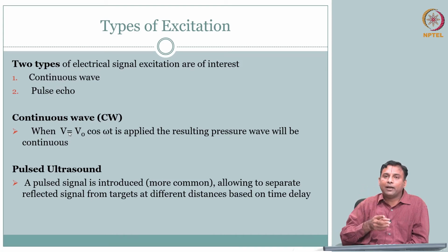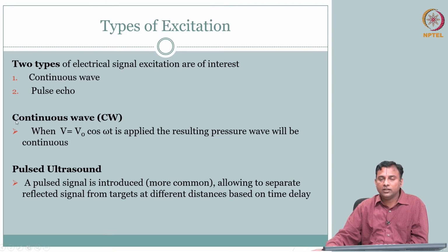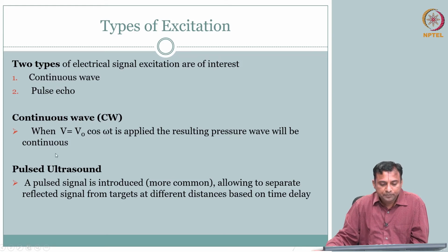So essentially what happens is, it is a continuous wave. They move around, and because of the Doppler principle, you hear a shifted Doppler frequency. It turns out that the Doppler shift is in the audible range, and therefore they use that. So continuous wave is useful, but predominantly for imaging purposes we use pulsed mode. Okay.